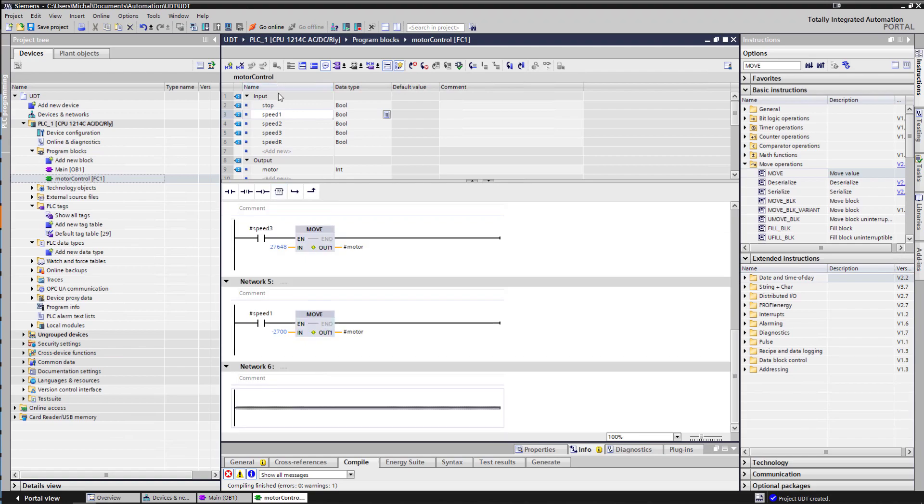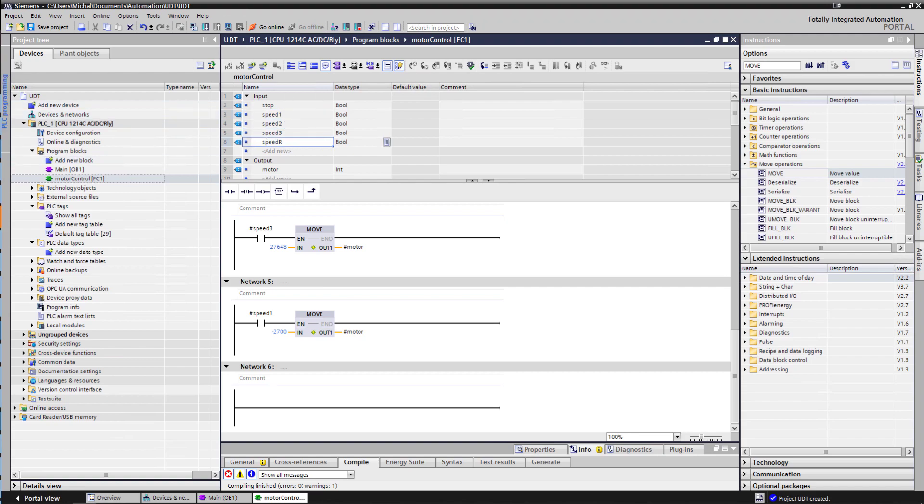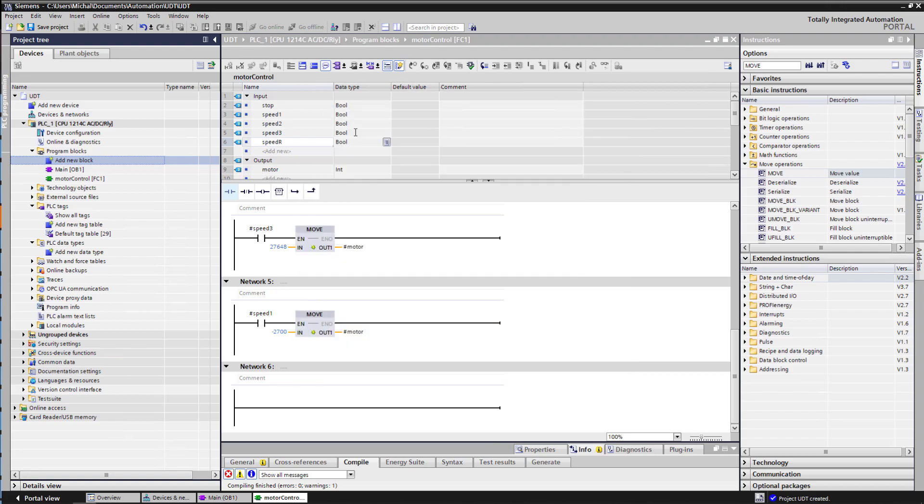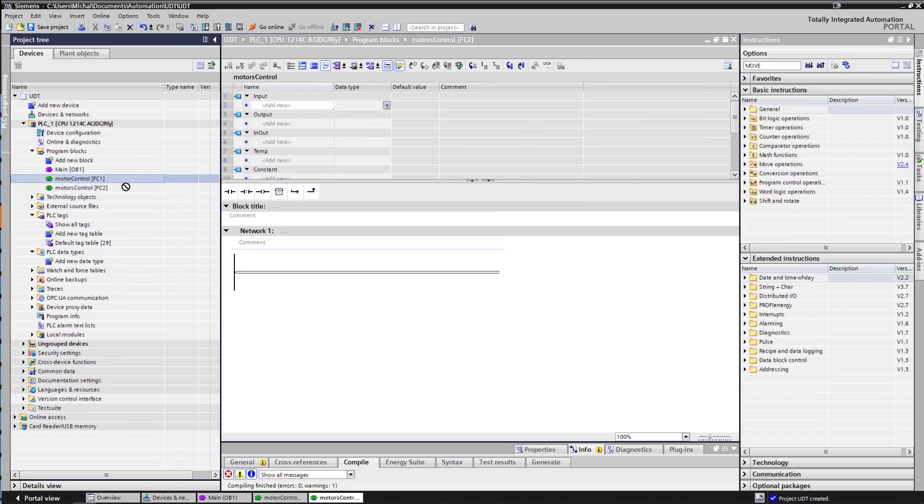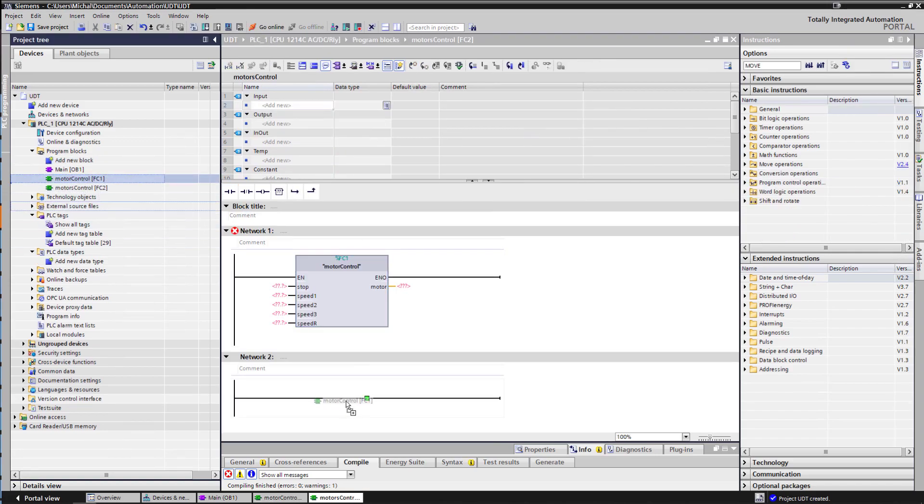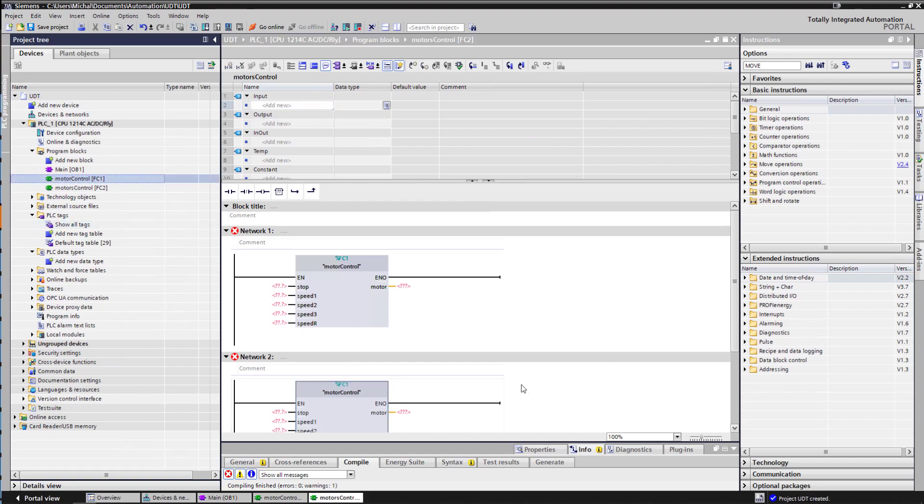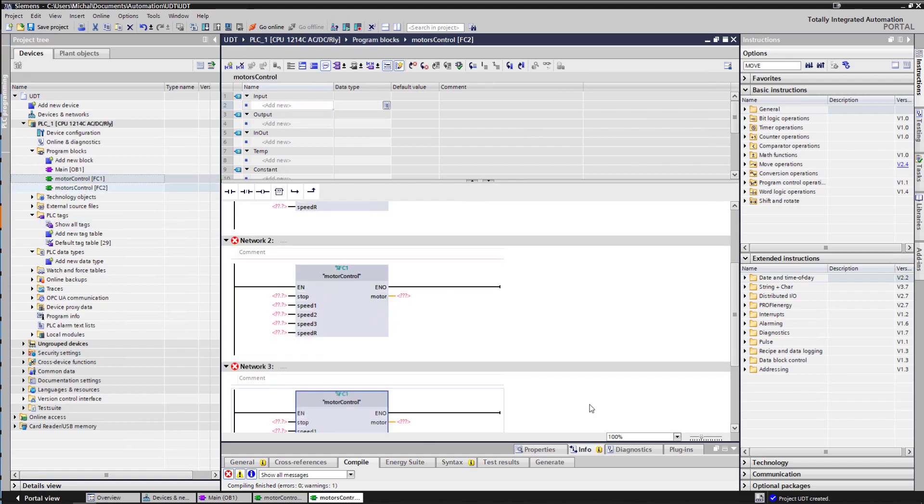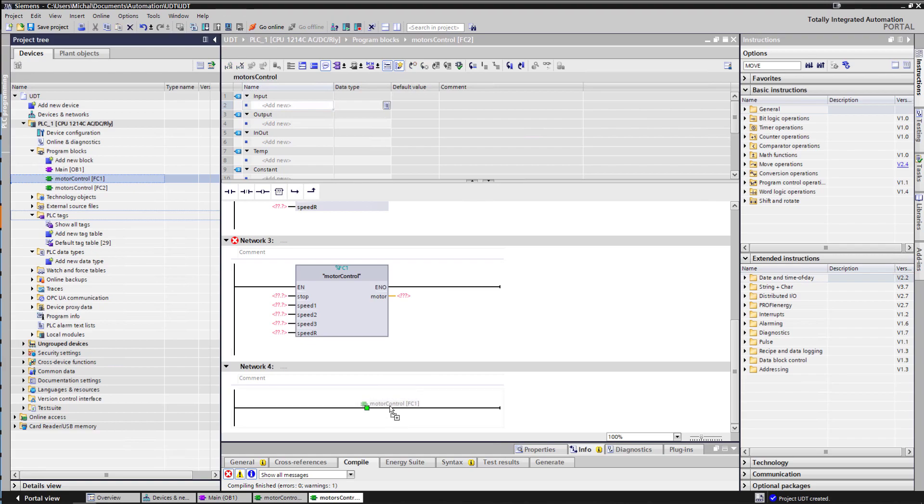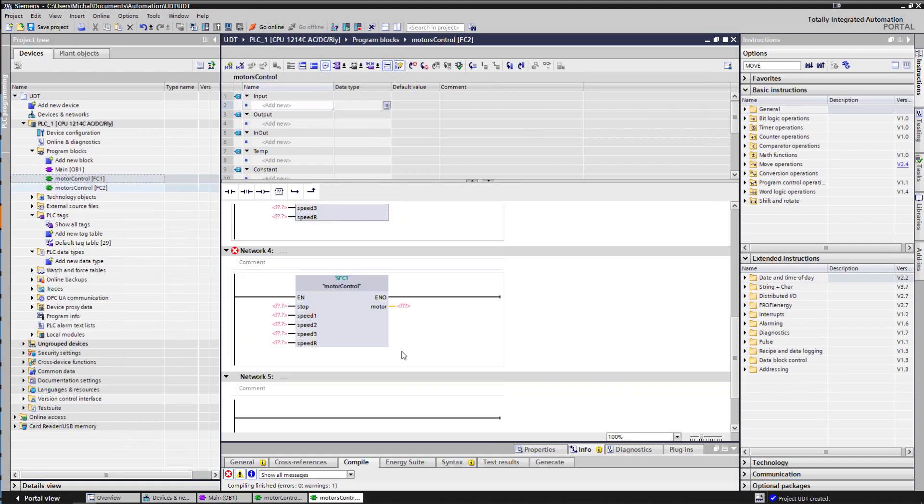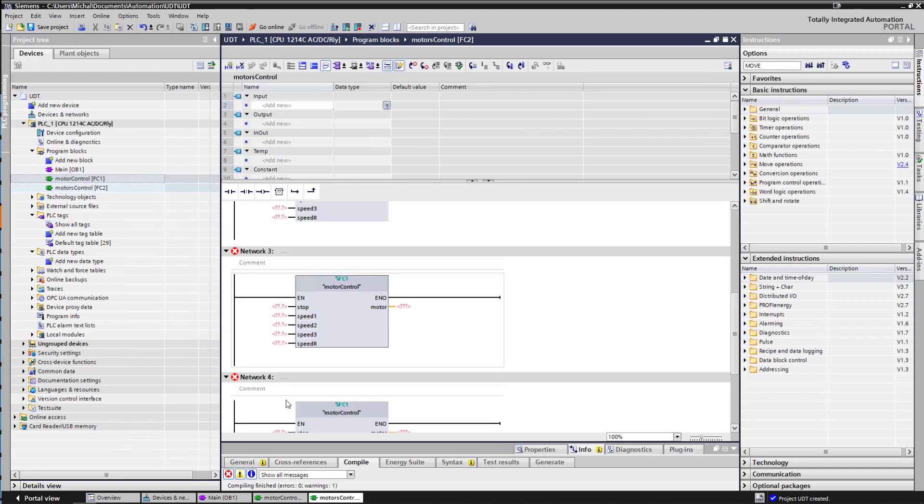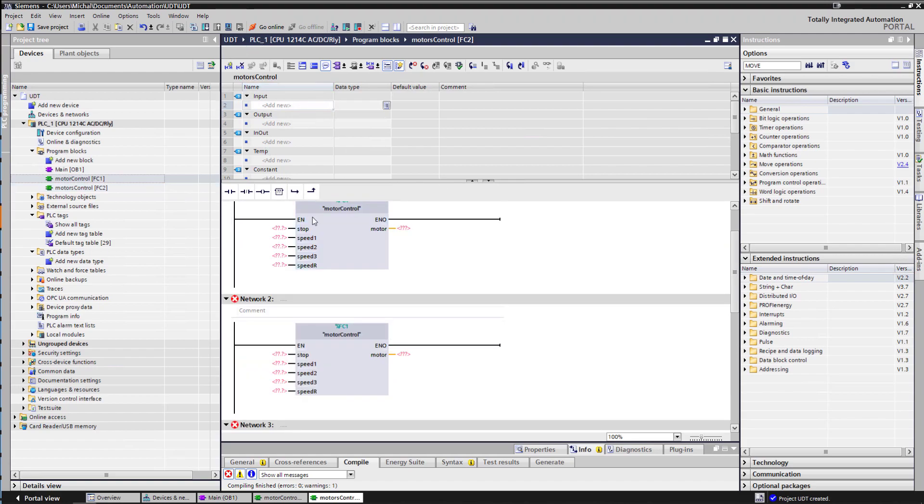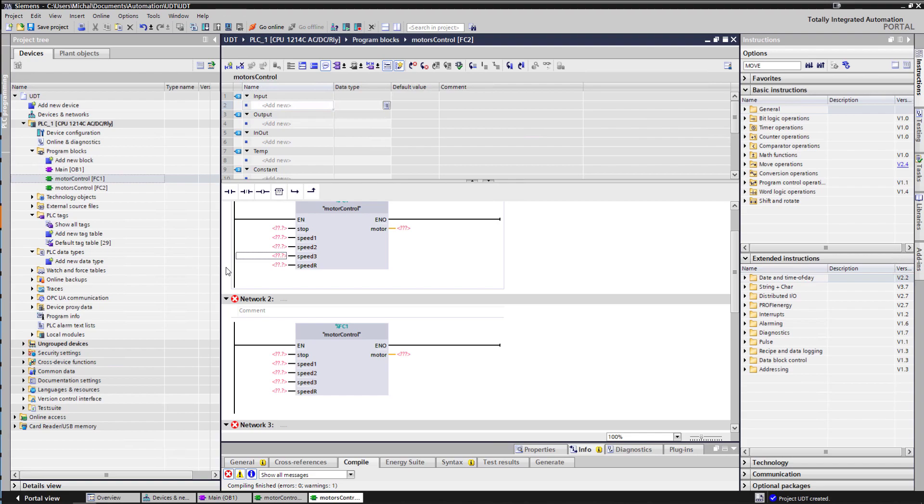The problem here as you can see is we already have five different inputs. Now this is for controlling a single motor but if I wanted to maybe make a function that's encapsulating it, so motors control in which I have multiple of these code, let's say I have four motors on site, I would already have to interconnect five times four, so 20 different variables from my inputs and this is where it stops being manageable and this is a very basic situation where I only have five different variables per block. So this is why we need structures, we need a way to just quickly send an entire variable and not worry about it.